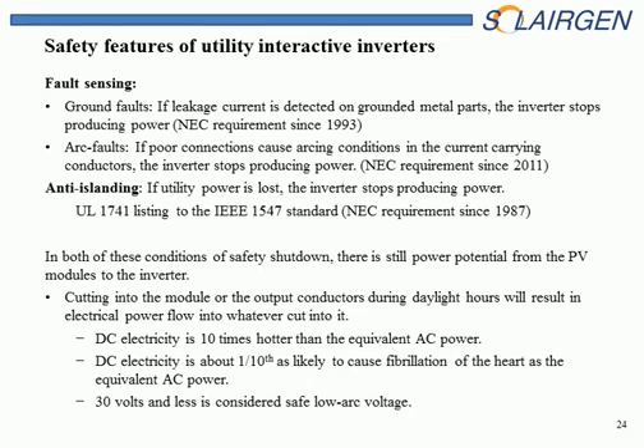We could have a rodent that has chewed through a wire or something, and the system's still operating and trying to produce energy, so it's arcing. So we want the inverter to shut down. So the arc fault protection device and the ground fault protection device shut down the inverter in case of these two events. The anti-islanding is where if the utility power is lost, the inverter stops producing power. This is to protect linemen, anyone that might be in the vicinity of a down power line.